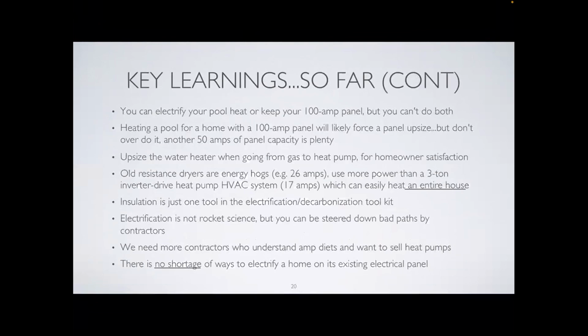Upsizing the water heater—when someone goes from, I think you noticed, we recommended going from a 50 gallon gas water heater up to an 80 gallon heat pump water heater. That's because the recovery time on heat pump water heaters is a little slower than gas, so we wanted to make sure they didn't run out. There's very little efficiency hit or bill increase; in fact they'll probably see a bill decrease going from the old gas water heater to the heat pump water heater. But there's very little penalty for upsizing the tank because the water heaters are so well insulated.